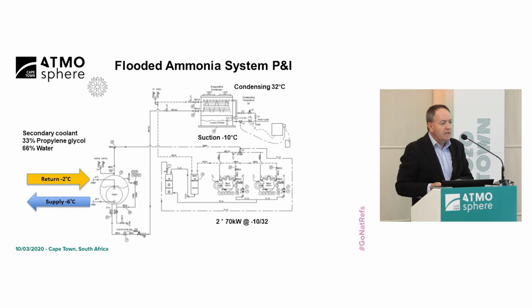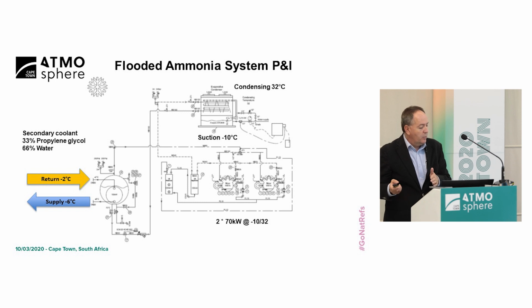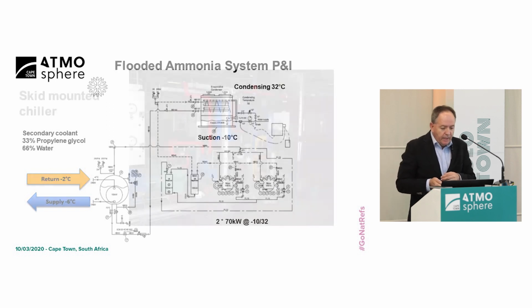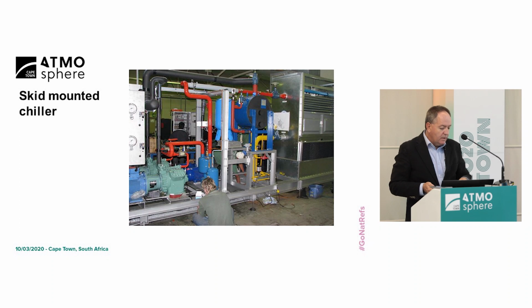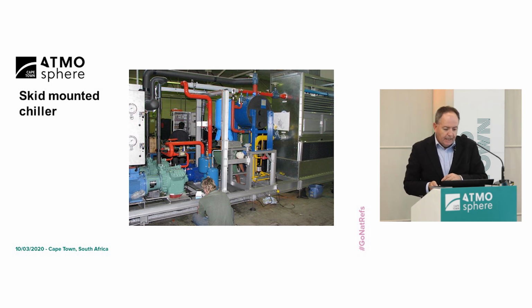And of course, the secondary coolant was water and propylene glycol. Ethylene glycol, I believe, is really toxic. So supply at -6, return at -2, two compressors at 70 kilowatt. That's basically what it looked like in our workshop. You can see we welded it all on a skid, and you can see the Bitzer compressors, the 6-cylinder machines at the corner at the bottom on the left-hand side there.